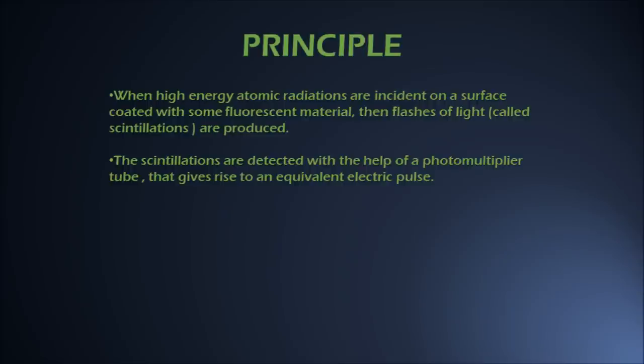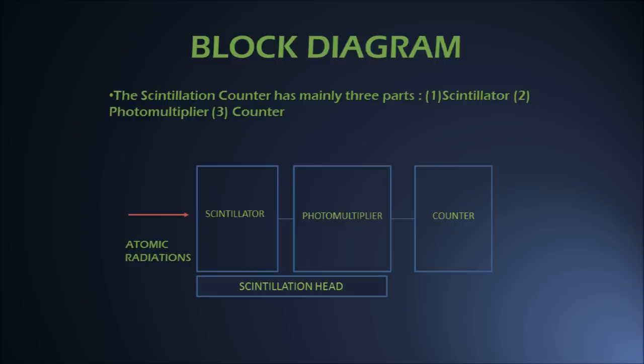Now let us come to the various major parts of a scintillation counter in the form of a block diagram. A scintillation counter mainly consists of three parts: number one, the scintillator; number two, the photomultiplier tube; and number three, the counter. The scintillator and photomultiplier tube can be collectively known as the scintillation head.